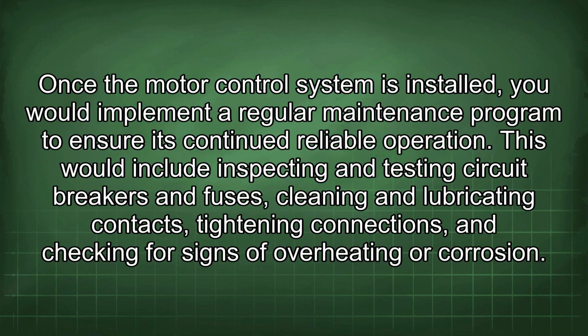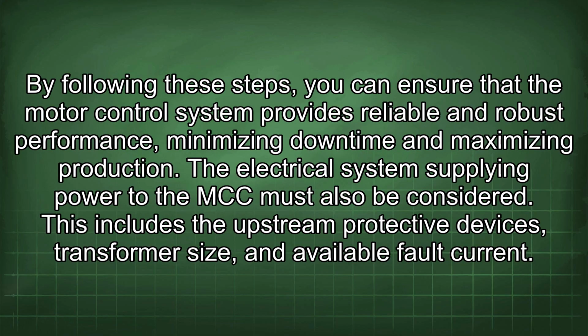This would include inspecting and testing circuit breakers and fuses, cleaning and lubricating contacts, tightening connections, and checking for signs of overheating or corrosion. By following these steps, you can ensure that the motor control system provides reliable and robust performance, minimizing downtime and maximizing production.